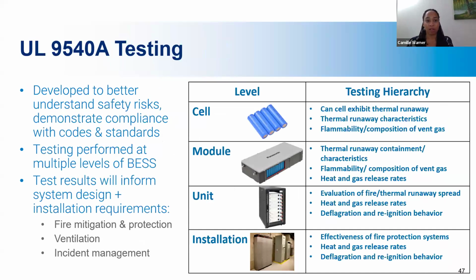So jumping into a little bit about 9540A testing: this is required by fire code for every large scale project, so 600 kilowatt hours or greater, tier 2 product. Smaller projects or products often opt to go through the test anyway for a number of reasons, including that they can have a relaxed code if the fire test can demonstrate that. We'll talk about that in a couple slides.